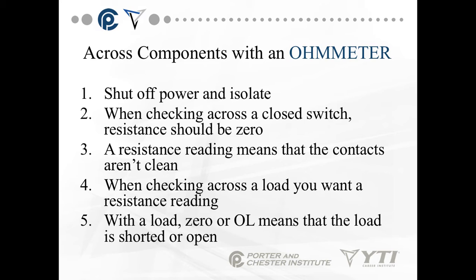When checking across a load, you want to have a resistance reading of some number. With a load, a zero, an OL, or infinite means the load is shorted or open.